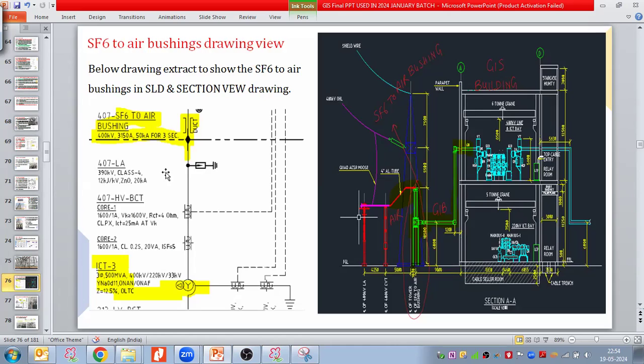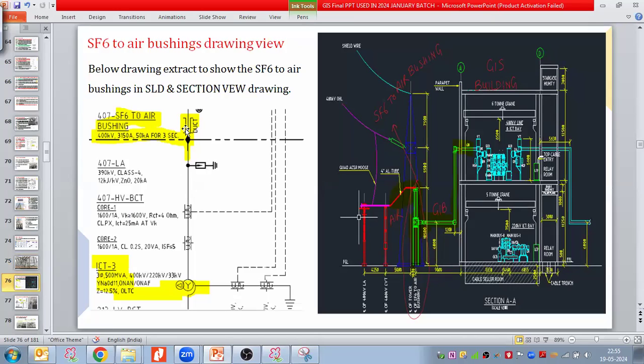If you see, I have taken another drawing, an SLD extract. In that we have indicated the duct. So this duct is representing this duct here, this kind of duct, which is represented in the drawing like this. And now the surge arrestor. So here we have this SF6 to air bushing. This is how we indicate it in the SLD.